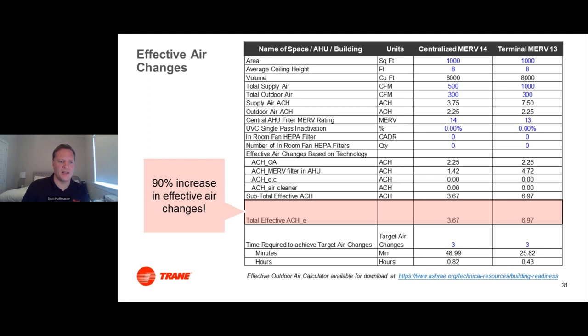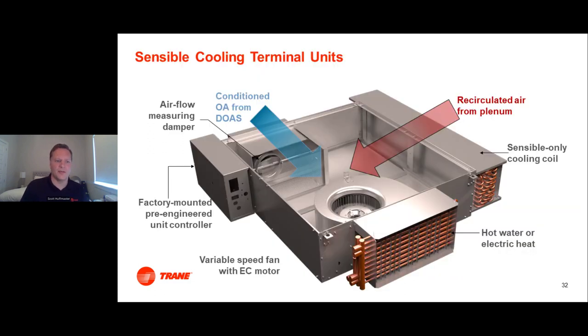I'm going to share one other piece here of what might be a system you would consider if your customer asked you for, give me the latest and greatest, best design you can think of for delivering on IEQ in a space. What I'm going to suggest to you is consider a system like a sensible cooling terminal unit system. What is a sensible cooling terminal unit system, Mr. Huffmaster? What this is, we're essentially combining a lot of the design aspects of a chilled beam system where you've got a sensible loop serving the space with a DOAS system that is also doing precision control.